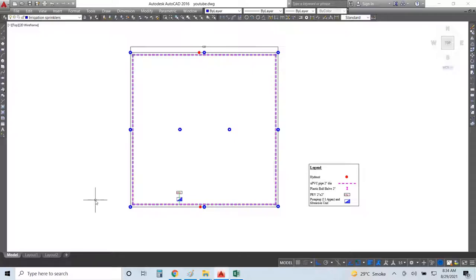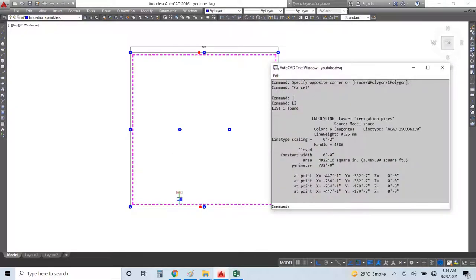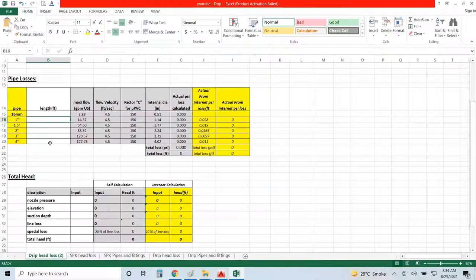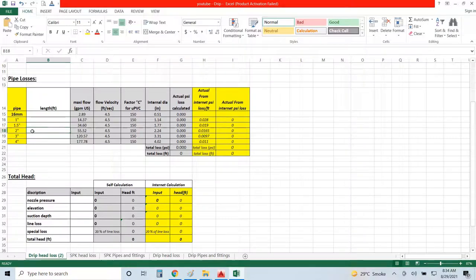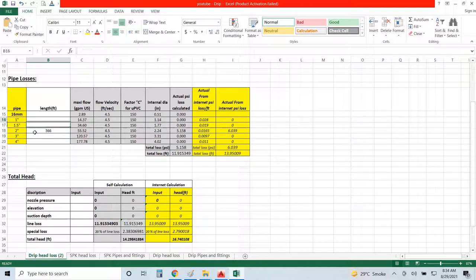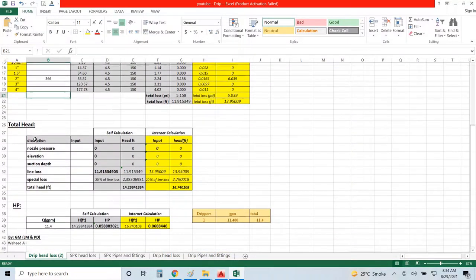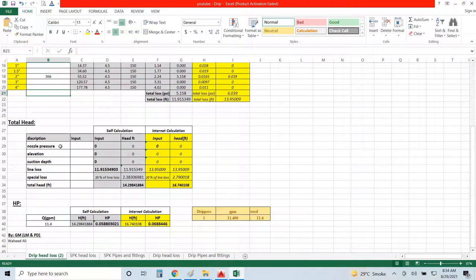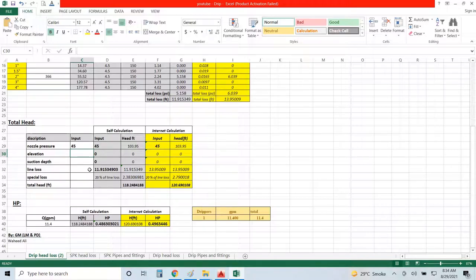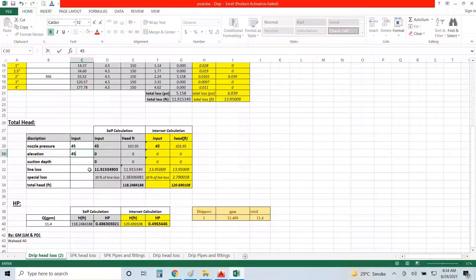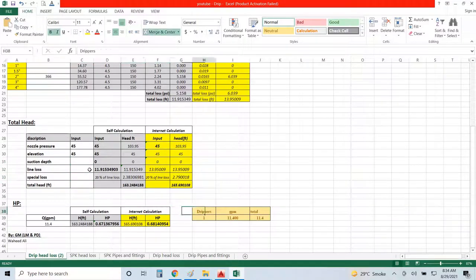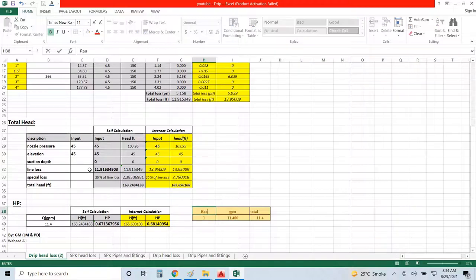Let's suppose we are designing for the rain gun. What is the length of this pipe? It's 732 feet. From here to there, it is almost half, so I'm going for 732 by 2. Nozzle pressure is about 45 psi. Elevation depth water source - let's suppose I am drawing water from a bore, so I have depth of water table about 40 feet, let's suppose 45 feet.